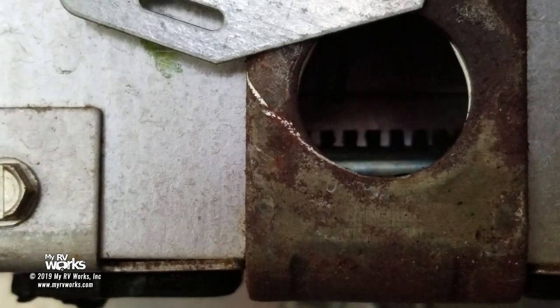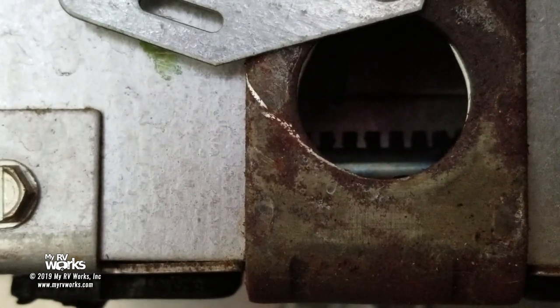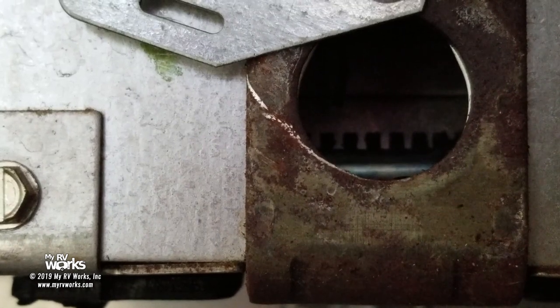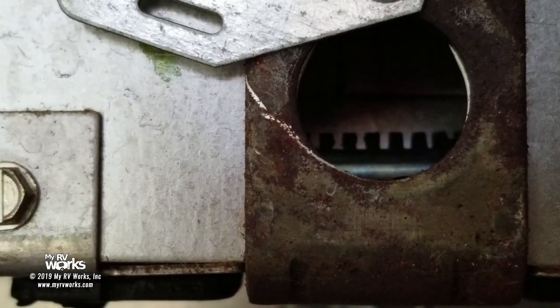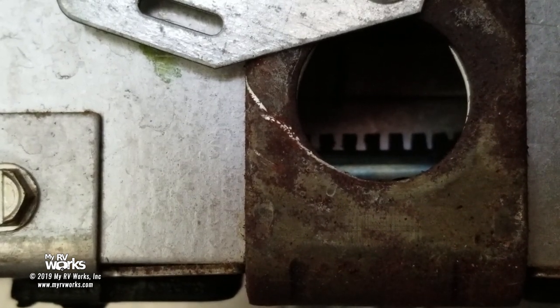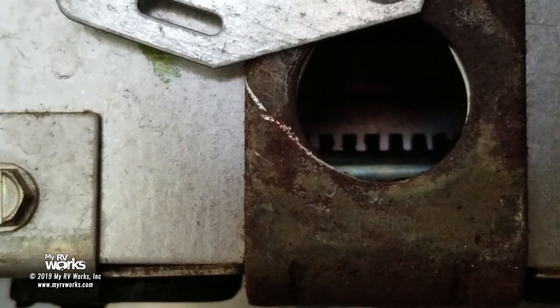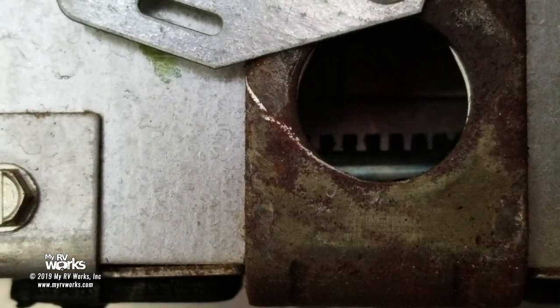And as soon as the gas gets introduced back in, it'll start itself. Or what may have just happened, you may have gotten a flame failure signal on the inside. You'll get that because your refrigerator's tried to start a few times and it just gave up. You have an FL? Uh-huh. Okay, off and back on again? Okay, so that's where your FL comes from. It flamed out, basically. So she's going to turn it off and turn it back on again.